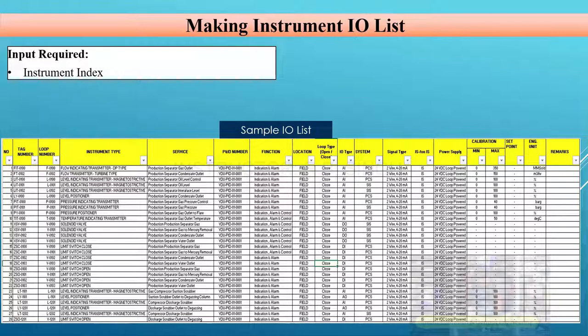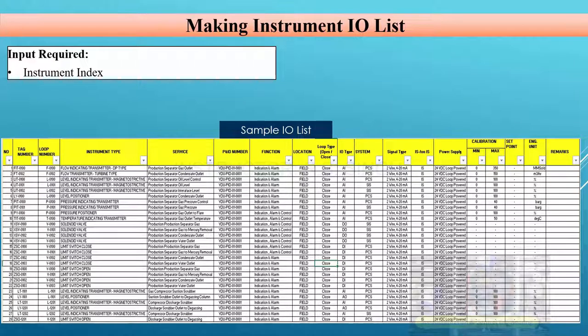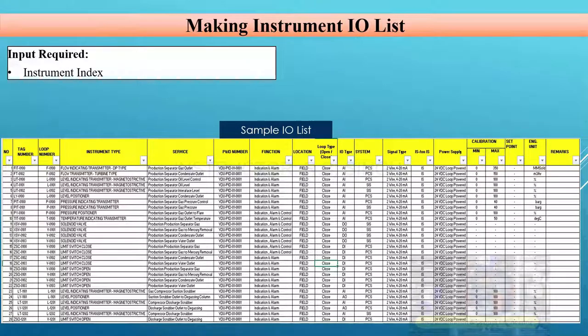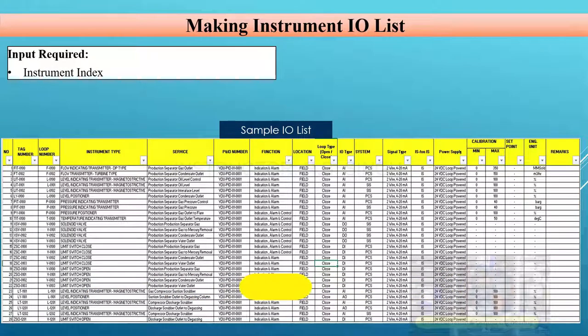In that closed loop, the pressure transmitter sends a signal to the control system, which sends a signal to the control valve. The functions include indication on the field and on the control system, controlling the pressure via the control valve, and generating alarms at set points. To check the function, you must refer to the P&ID, where the types and number of functions are clearly mentioned.